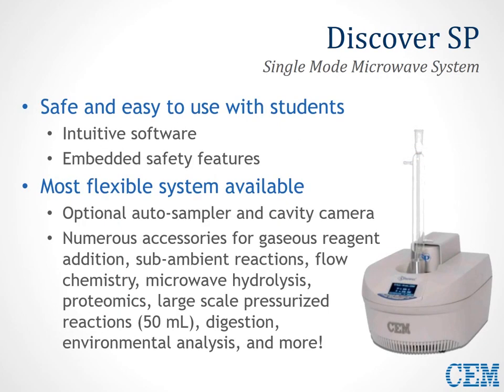Safety is always a concern in teaching labs, which is why there are several embedded safety features in the Discover SP. The intuitive software and active vent pressure device comes with temperature and pressure release limits, protecting users from exposure to vented gas and hot vessels. The cooling feature ensures the vessel is at a safe temperature for removal at the end of your reactions. If an accident should occur, all debris is contained within the cavity and can be cleaned up in just a few minutes — simply remove the spill cup, clean up, and you're ready for another run. No tools necessary.